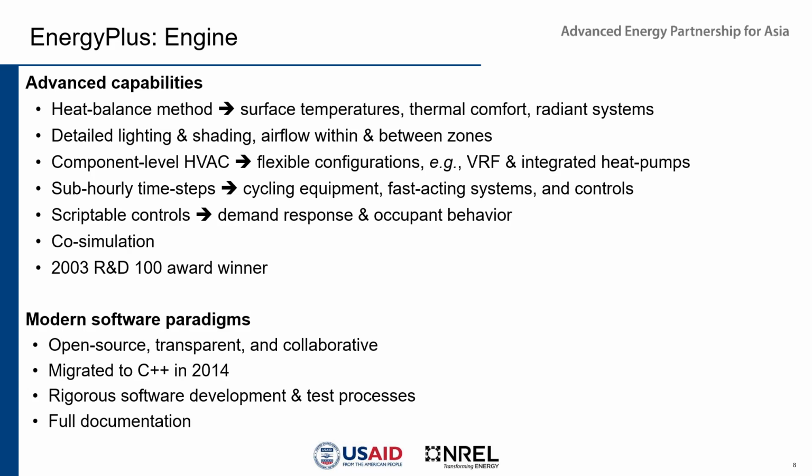But the capabilities of EnergyPlus here: it can determine, using essentially energy conservation, what we call the heat balance method, surface temperatures. We can determine thermal comfort. We can consider, for example, radiant systems. It involves lighting and shading, airflow within and between zones. It looks at component level mechanical systems. So different aspects could be considered, such as VRF, or variable refrigerant flow, and integrated heat pumps.